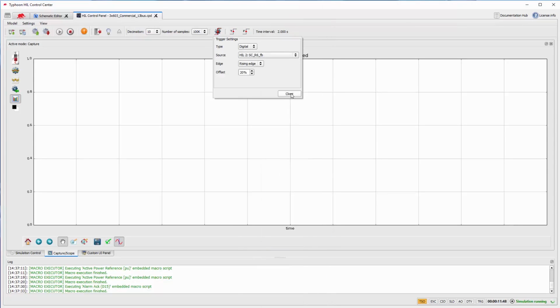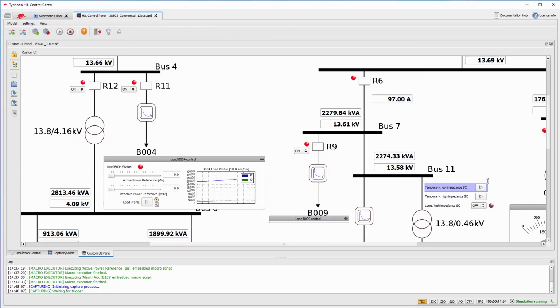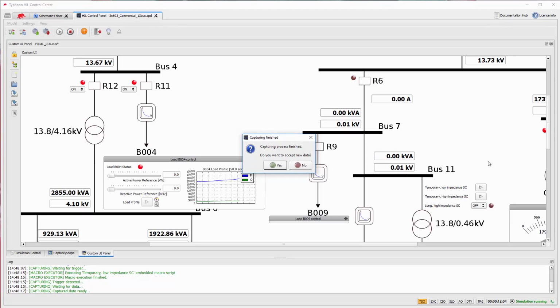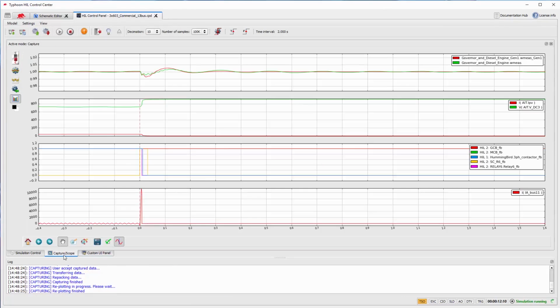First, let us set the trigger for the low impedance short circuit contactor called SCR6. The impedance of this short circuit is 0.9 ohms, and its expected current is 11 kiloamps. Let us enable the trigger, cause the fault, and take a look at the waveforms captured. As expected, the short circuit current was around 11 kiloamps.